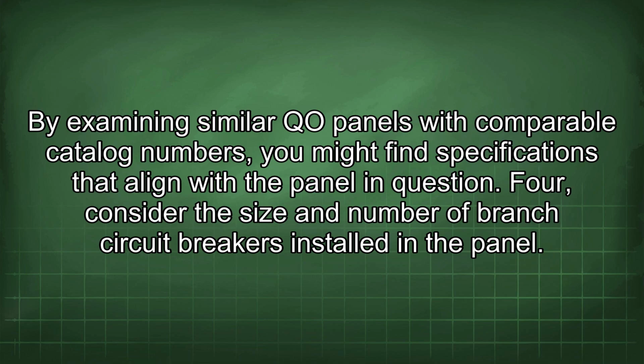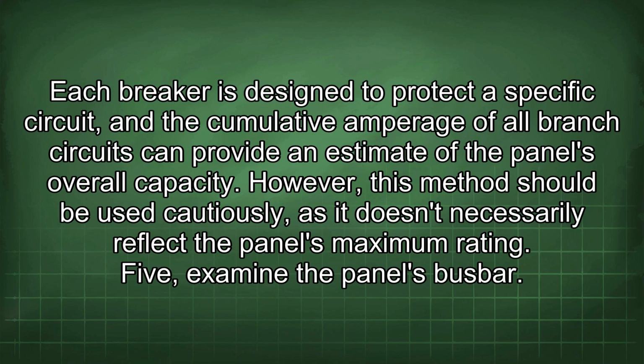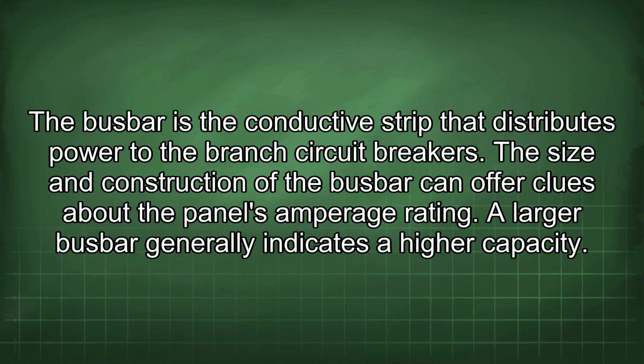4. Consider the size and number of branch circuit breakers installed in the panel. Each breaker is designed to protect a specific circuit, and the cumulative amperage of all branch circuits can provide an estimate of the panel's overall capacity. However, this method should be used cautiously, as it doesn't necessarily reflect the panel's maximum rating. 5. Examine the panel's busbar. The busbar is the conductive strip that distributes power to the branch circuit breakers. The size and construction of the busbar can offer clues about the panel's amperage rating. A larger busbar generally indicates a higher capacity.